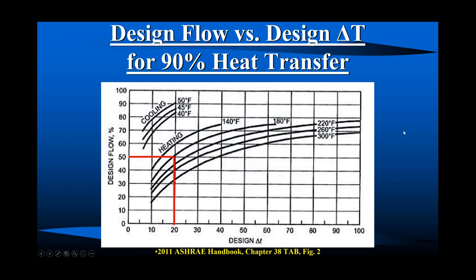Let's take a look at a chilled water system. That was a 10 degree delta T system and 45 degree supply. All right, just a little bit less tolerant of a lack of flow. So we need to get 90% out of that coil. We need 7 GPM if I needed 10 on design day. Let's take a look at another system. There's our 30 degree delta T system with 150. That is a very difficult system to balance. Much more difficult than the 180 to 160 system.